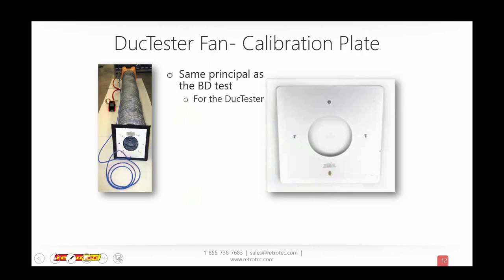I don't know, it's sort of a great segue from that last question. But here's a hole, and it's pretty simple. You just set up the duct tester as you would if you were attaching to a return in a house. But here we attach it to the calibration plate, and you can see right here that we have our blue hose, or our input hose, connected right here to the plate. So we've run our blower door, and this is a known hole of a known size, and we just calibrate, or see if our fan's in calibration for that.